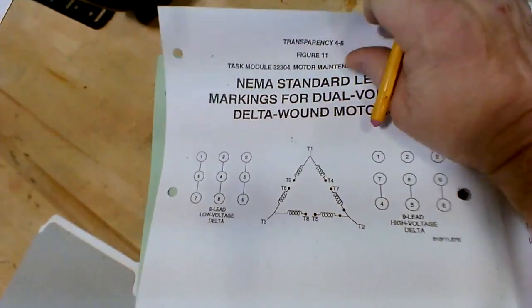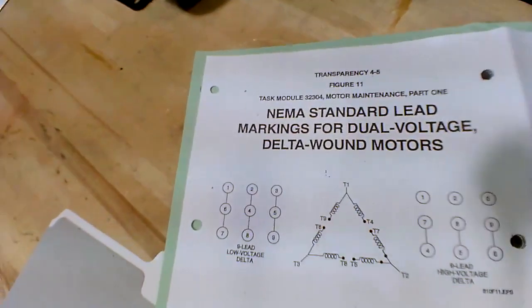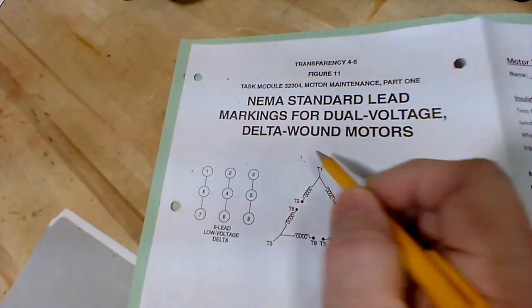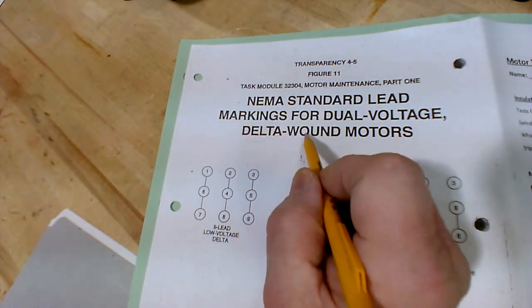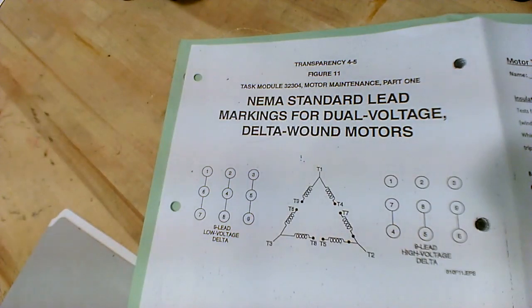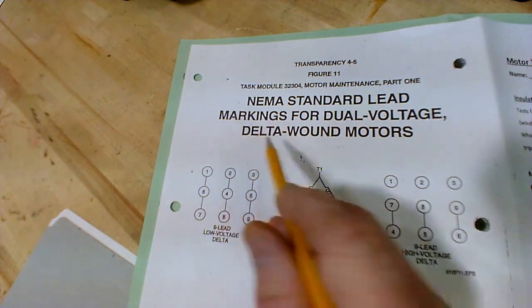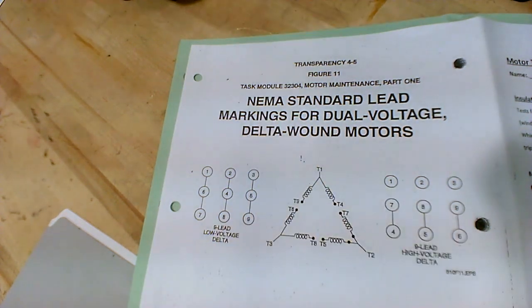Delta looks like a triangle. And when you see a delta wound motor, then it actually tells you the word delta. It'll say delta wound right on the nameplate. I've got one we're going to show you back in the cabinet. We're going to do that really quick here in just a second. Show you every delta motor I've ever seen in my life, which is not a lot of them. They always tell you that it's delta right on the nameplate. It says delta wound. It tells you right on there.